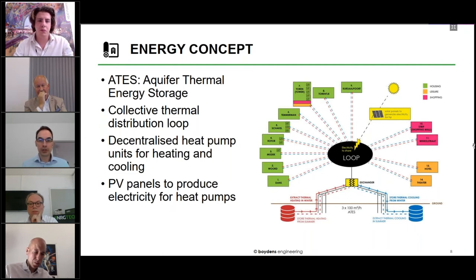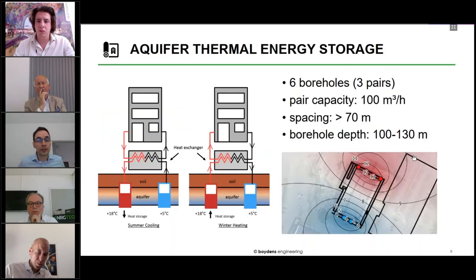You can see here on the picture how different functions of the buildings are connected to one loop, which is acting as a central way of distributing the heat from the ground source heat exchanger towards the buildings on the site. Now, about the aquifer thermal energy storage system, what this allows us is that, depending on the season, so it's either summer or winter, one can inject the heat in one of the boreholes that are on the site.